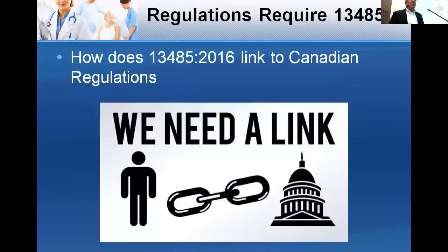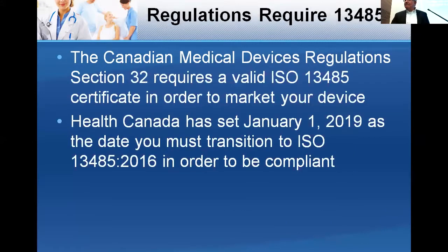Just 2 minutes here on the linkage to the Canadian regulations. Section 32 of the medical device regulations requires you, as a manufacturer, to submit a copy of your ISO certificate with a scope that matches the device you're submitting for licensing at the time you submit it to Health Canada. As of January 1st, 2019, Health Canada will only accept 2016 certifications.